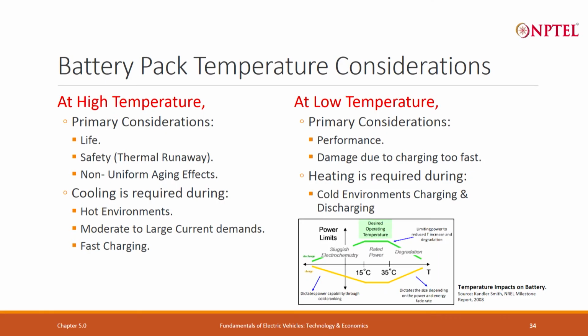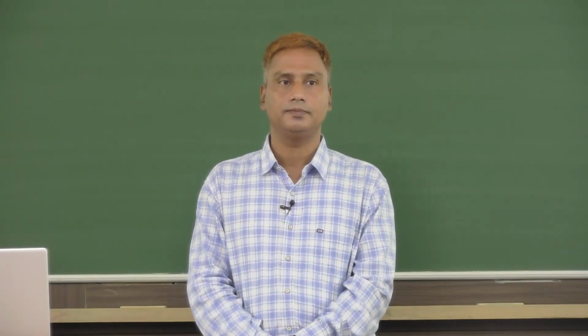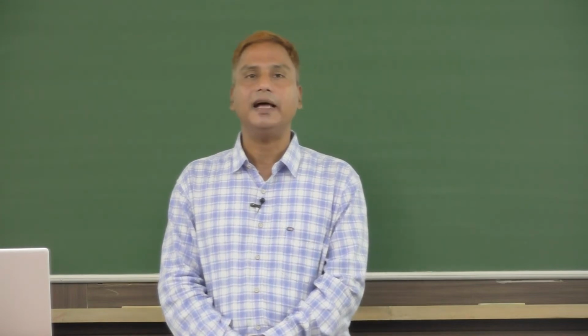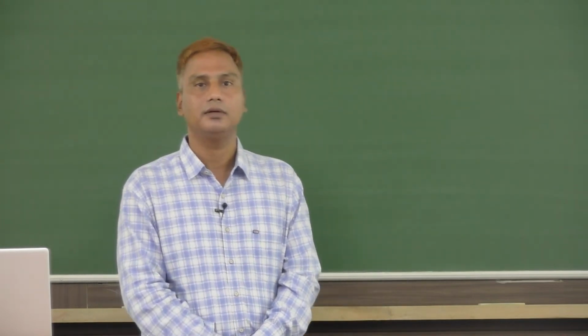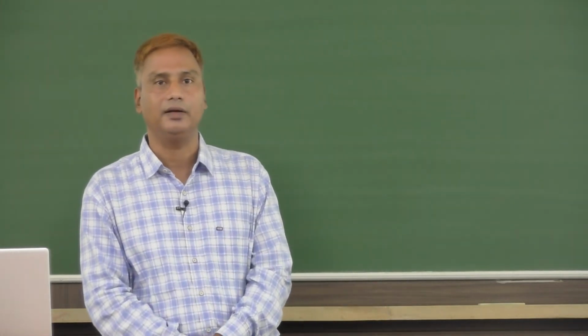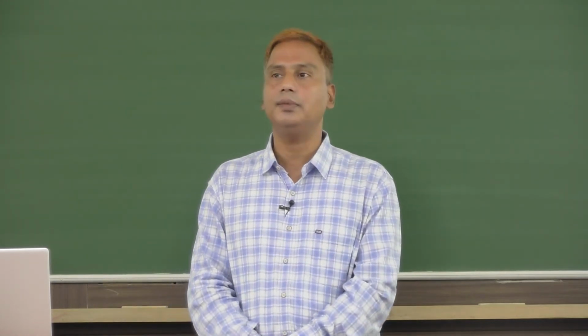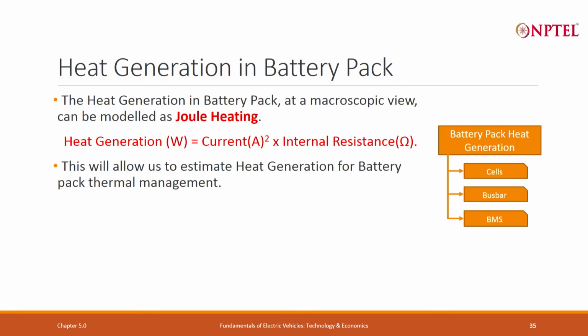So when heating is required in cold environments like Leh and Ladakh, Jammu and Kashmir, or Ooty during winter, where temperatures tend towards 0 degrees or sub-zero, we require a heating arrangement in the battery to maintain the temperature between 15 to 35 degrees. Now, how is heat getting generated in the battery pack?